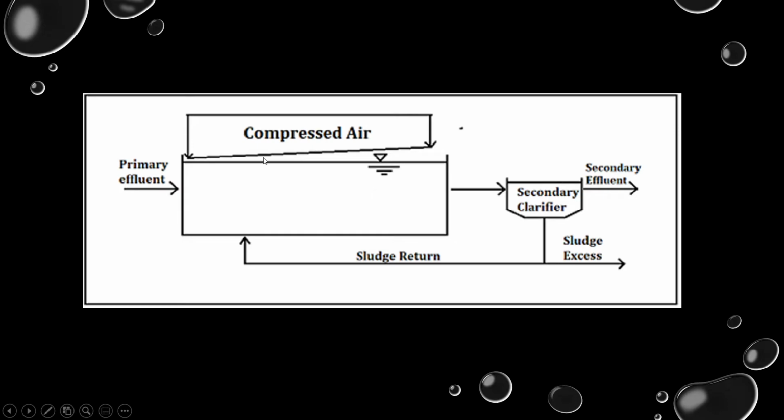We provide a high amount of air near the inlet for the reason that it helps the microorganisms grow more rapidly to match the BOD concentration at the inlet. So, the more the effluent traverses along the tank until it reaches the outlet, the BOD concentration gets smaller and smaller, since we provide a low amount of air that matches this BOD concentration.